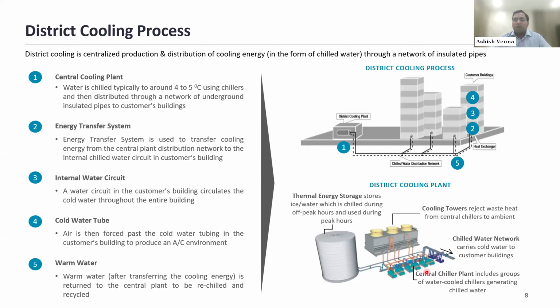A major component of district cooling plants is the thermal energy storage tanks. Thermal energy storage is what Dr. Garg spoke about. There are multiple types of thermal storage tanks, which I will cover in the next slide. Mostly the purpose of these tanks is to store chilled water or ice during off-peak hours, when the electricity tariff is on the lower side, and then use it during peak hours. So it helps reduce the peak power consumption of the cooling plant.